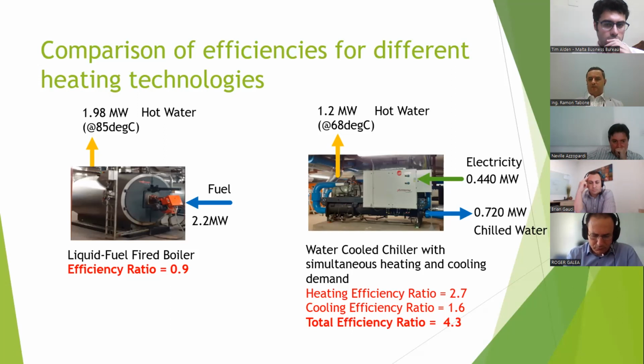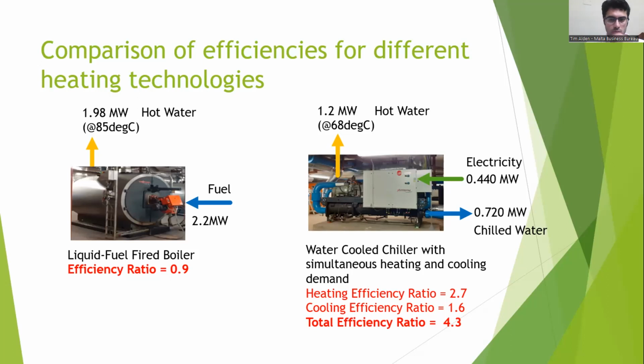What happens in our water-cooled chillers? We're giving 0.44 megawatts of electricity, and we're getting 1.2 megawatts of hot water. At the same time, we're getting 0.72 megawatts of chilled water. So if you work out the heating efficiency ratio, we're getting 2.7 times as much, and the cooling efficiency ratio is 1.6 times as much. This makes the total efficiency of the machine 4.3 times as much.